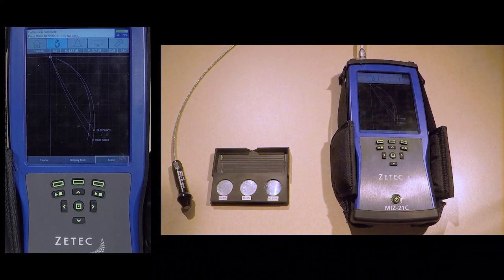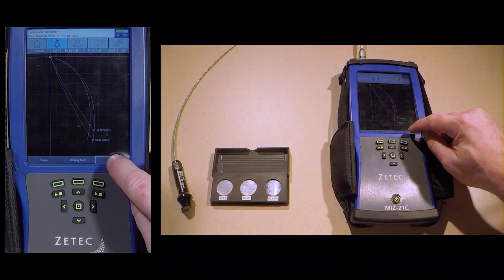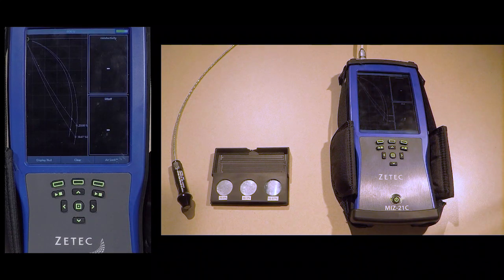The conductivity and liftoff can also be read directly. Calibration is now complete. A visual representation of the conductivity curve will now be shown. Tap Done in the lower right corner to complete the calibration process.